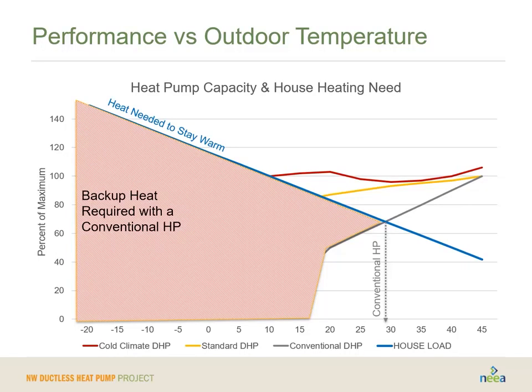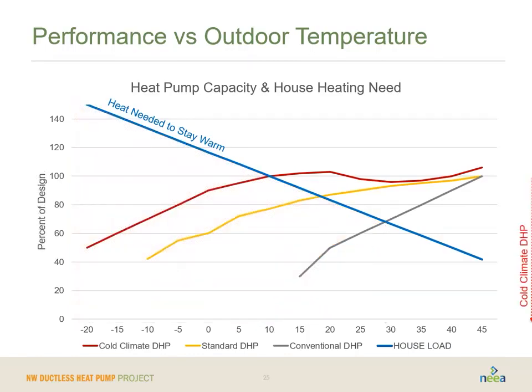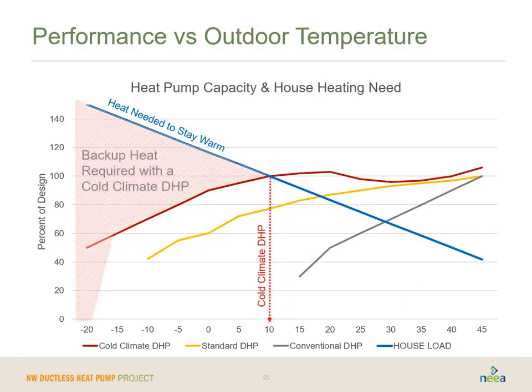But variable capacity cold climate heat pumps, on the other hand, are able to operate all the way down at, say, 10 degrees. And in this scenario, you only need a small percentage of the time to be treated with backup heat. So you tell me which you'd rather have: a heat pump that can do heating and cooling for the lion's share of the year and only needs backup heat for a very small amount of time, or the previous one that we saw, where a lot of the time you still had to have backup heat provided even though you had a heat pump.